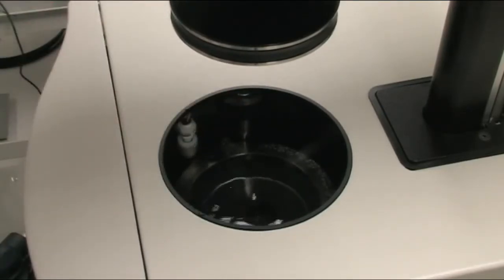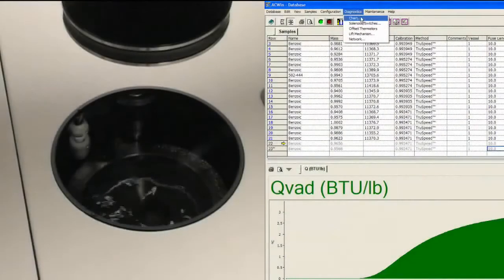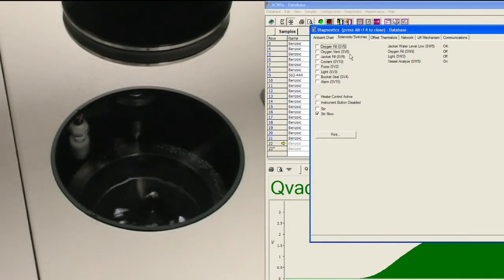After you're sure that there are no bubbles present on the inside of the baffle, you want to go to your diagnostic screen, open solenoids and switches, and increase the stir speed. Make sure that you increase it and start to form a vortex on the inside of the bucket. If the unit increases in speed and you get the vortex formed, you want to set it to stir slow and let the system equilibrate.